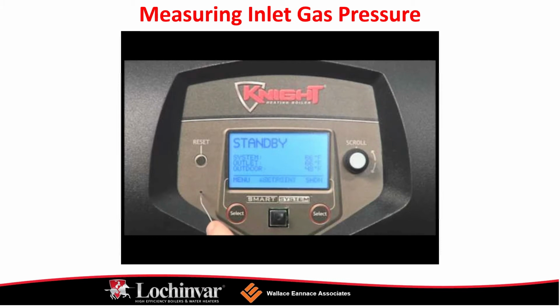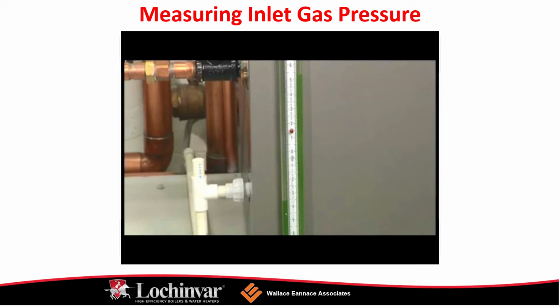Using a screwdriver, loosen the set screw at least 1 full turn. Connect a manometer with a scale up to 14 inches water column to the fitting on the gas valve. Turn on the main gas supply to the unit at the external main manual gas valve. Observe the static gas pressure on the manometer. For natural gas units, the inlet gas pressure should be between 4 inches water column and 14 inches water column. For propane units, the inlet gas pressure should be between 8 inches water column and 14 inches water column. If the inlet gas pressure is not within these ranges, contact the gas utility, gas supplier, or installer to determine necessary steps to provide proper gas pressure to the unit.